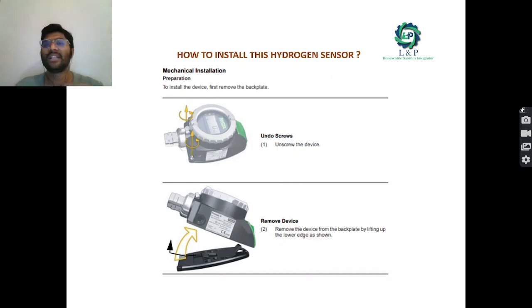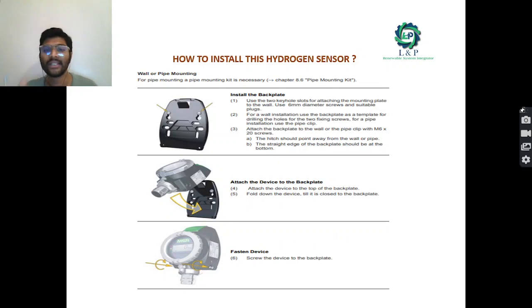How to install this hydrogen sensor? First let us see how it is mechanically installed. First and foremost, we need to undo the screws, unscrew the device, and remove the device backplate. The next thing is that we need to install the backplate. We can do two sorts of mounting: either wall mounting or pipe mounting. What sort of screw sizes can we use? You can use 6 mm diameter screws, which are very suitable for its two plugs. Most importantly, if you want to attach the backplate to the wall or the pipe clip, you can use M6 by 20 screws. Most importantly, the hinge should point away from the wall or the pipe. Once it is fixed, you can attach the device to the backplate properly and then fasten the screws back.